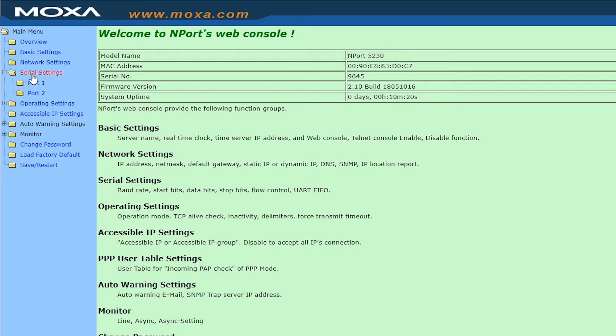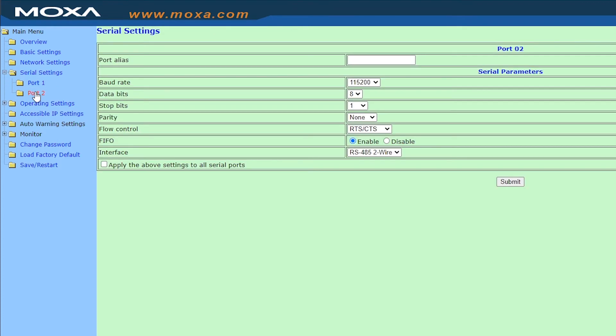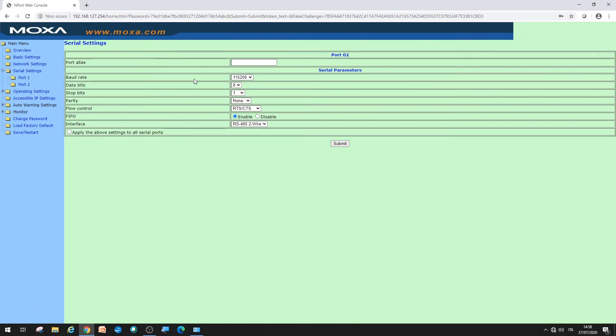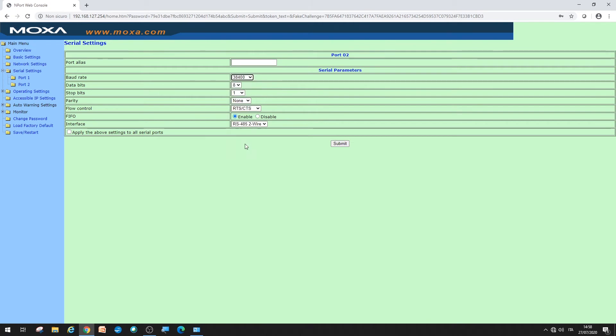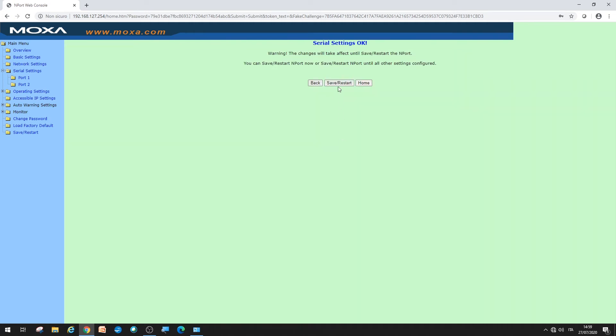In serial settings, for port number two, set the baud rate to 38400 and the flow control to none. For the other parameters, leave the defaults. Press submit to save and restart.